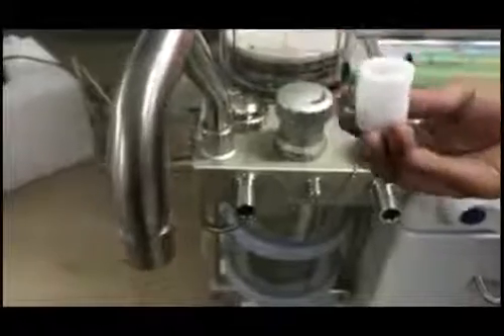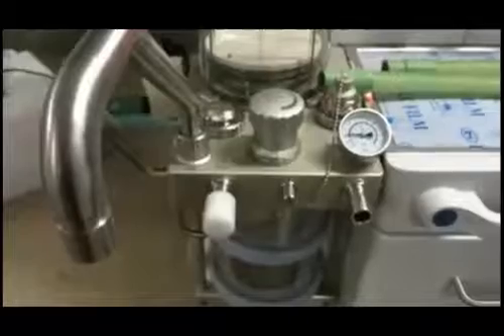The next step is to disconnect the hoses from the inspiration and expiration ports. This is the expiration port. You can use this blocker to block the expiration port. After this step is complete, now we will remove the bellows. To remove the bellows, the first step is to remove the bellows cover. After removing the bellows, please place back the bellows cover.